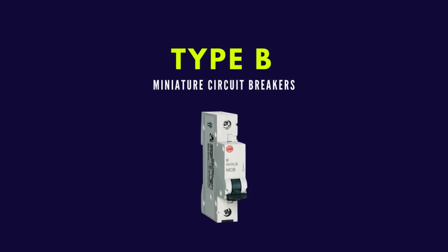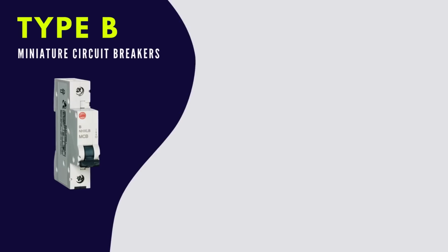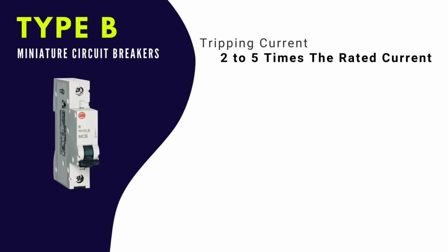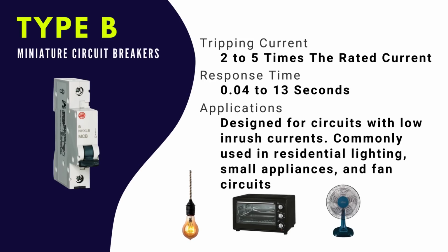Next, let's talk about Type B MCBs. These trip at 3 to 5 times the rated current and are designed for circuits with low inrush currents. The tripping time can range from 0.04 to 13 seconds, depending on the fault current. Type B MCBs are commonly used in residential lighting, small appliances, and fan circuits.